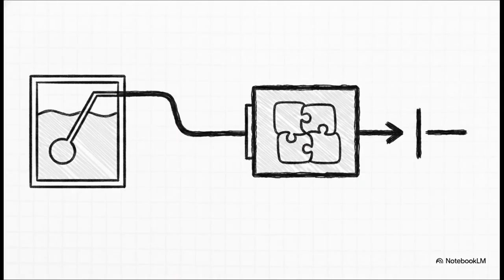Okay, so here is how that hardware to software pipeline actually works. When the float switch drops inside the Buchholz, it closes a very simple electrical contact. We wire that contact right into the back of the RET615 as a binary input. Just a simple 1 or 0, on or off. Then, inside the relay's software, that binary signal gets handed to a specific logic block called MAP-GAPC. That stands for multi-purpose protection. Basically, MAP-GAPC translates that raw mechanical trigger into a standardized digital signal the rest of the relay can actually understand.